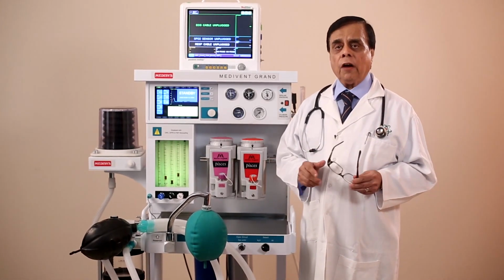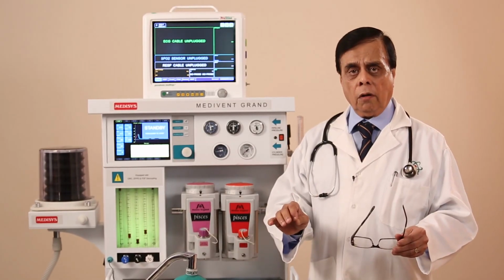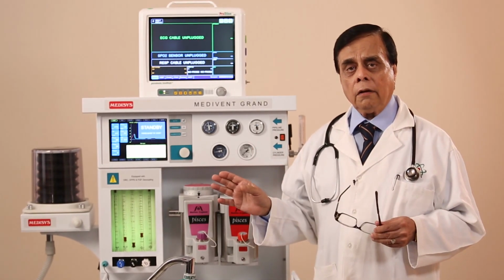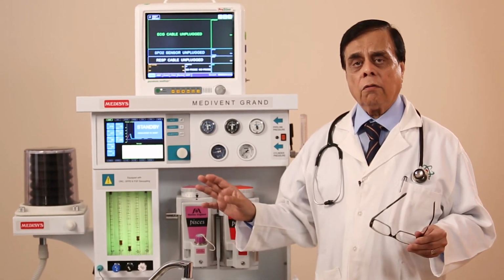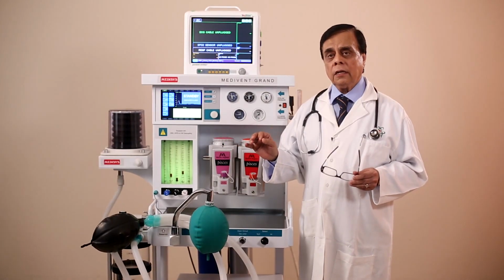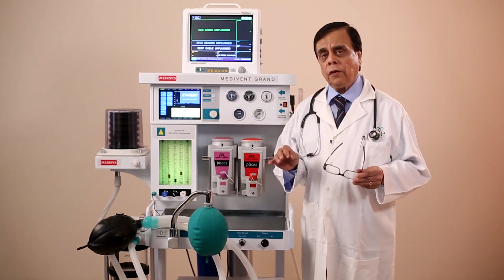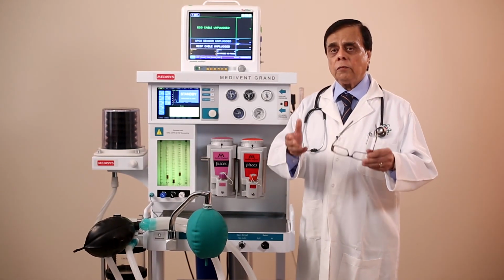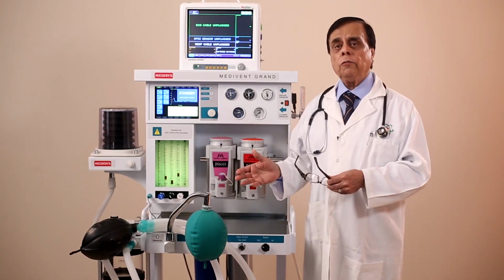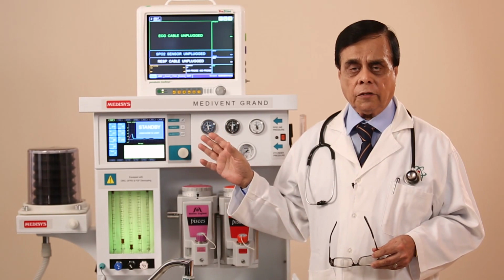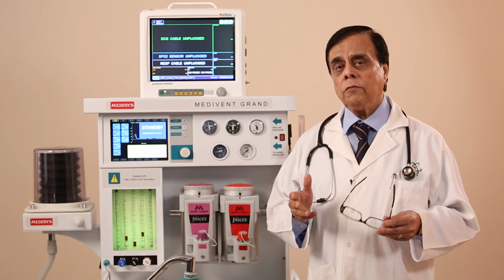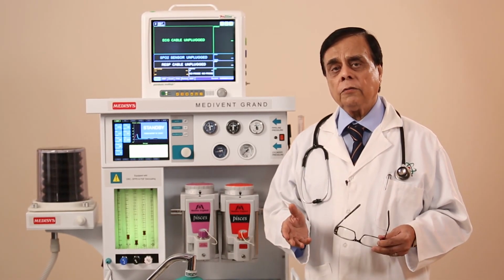So along with these safety devices, we have added a few more. One of them is that when you are using air, you cannot put nitrous oxide on. This is a very useful device. And the second safety device, which is very specific to us, is that as the characteristics of the patient's lung change, our machine will also adapt to that. I will come to that when I discuss the ventilator after this. And second is the capability, that is the main thing we are doing: giving a ventilator which is equivalent to any critical care ventilator available today.